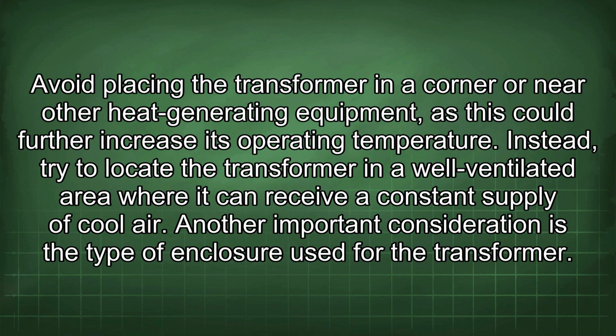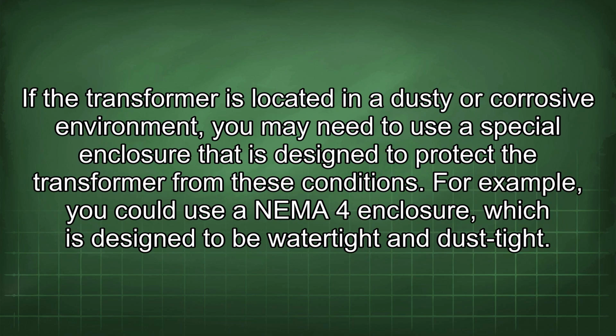Another important consideration is the type of enclosure used for the transformer. If the transformer is located in a dusty or corrosive environment, you may need to use a special enclosure that is designed to protect the transformer from these conditions. For example, you could use a NEMA 4 enclosure, which is designed to be watertight and dust-tight.